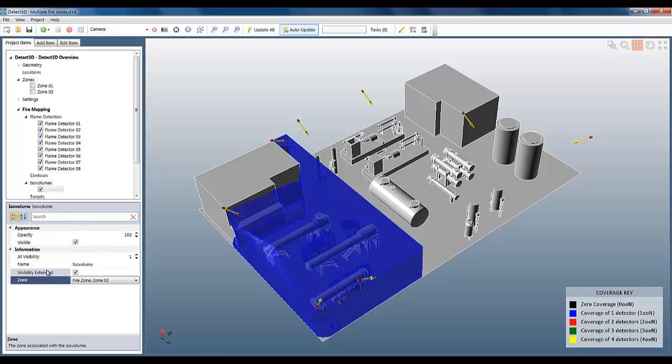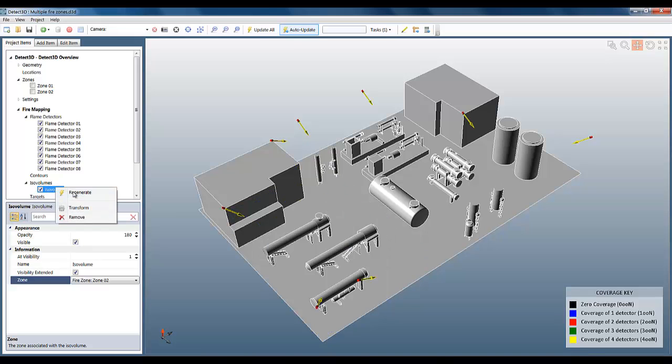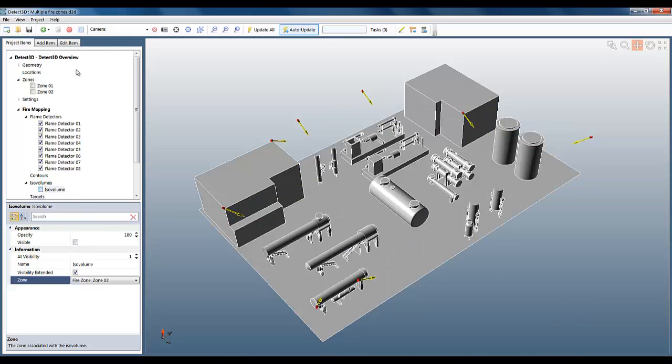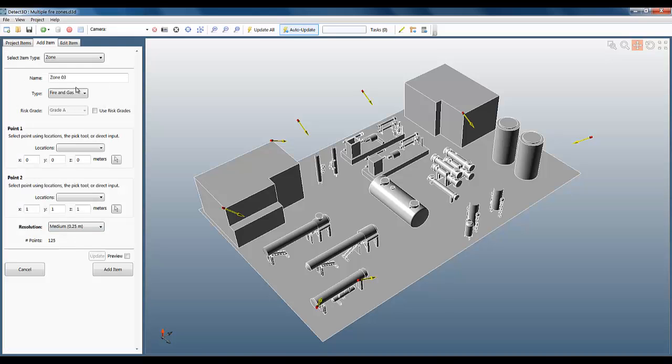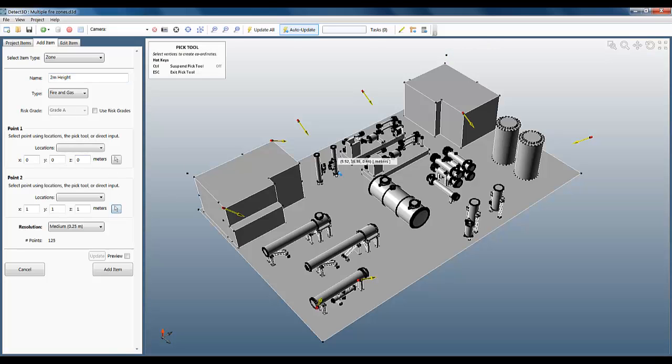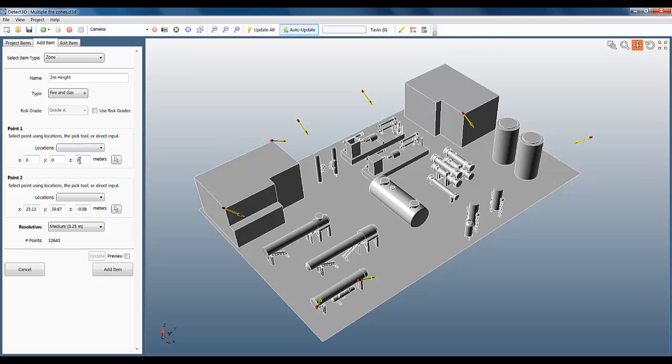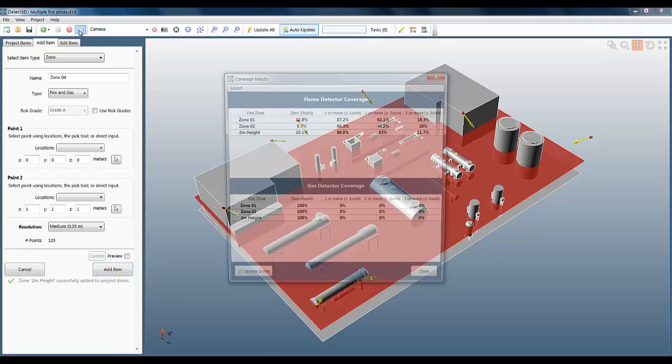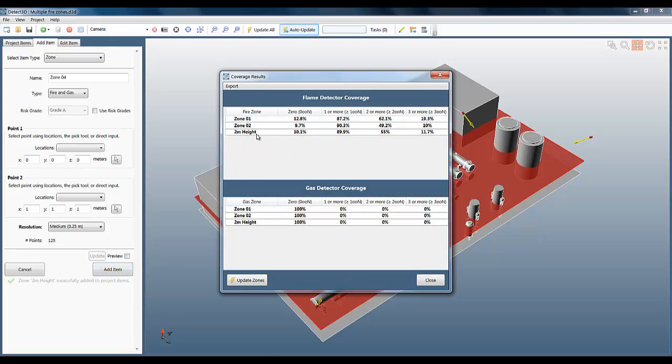It's also helpful if I want to see the coverage results at a certain height above ground level. For example, if I wanted to see the statistics at 2 meters height, I can just add a very thin fire zone at this height. I'm selecting the z-coordinate to be between 2 and 2.1 meters. And once that's added to the project, I now have the coverage results at 2 meters height. So very simple and quick, but a very powerful capability to define multiple fire zones in a single project.